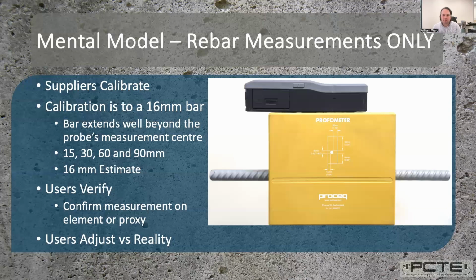So if we don't meet any of those criteria, we'll adjust the device until it meets those criteria. And that is a fixed process. That is what the supplier or a manufacturer will do to confirm the machine is operating like all the other PM8000 cover meters in the expected window of performance. Now, you could buy a calibration block. It's not really necessary unless you'd like to run an internal calibration process using a traceable reference, because for a user, a verification and an adjustment is a more useful job.